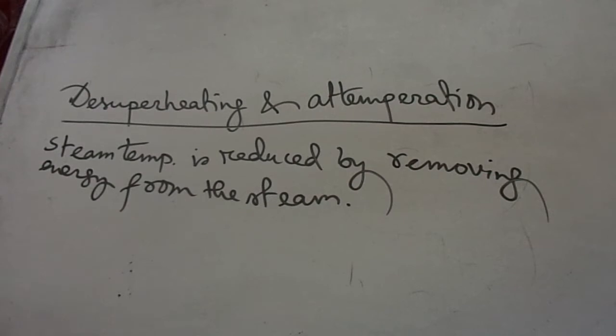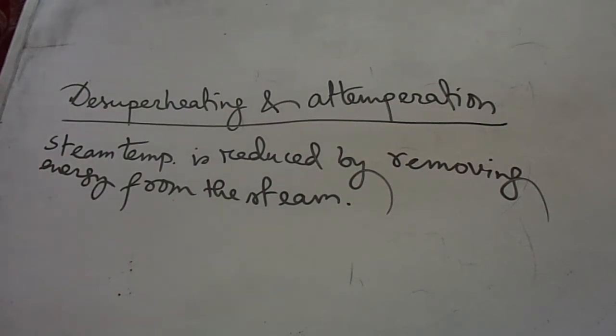In the tubular type, a portion of steam is taken out through tubes from a point between the primary and secondary superheater by an automatic valve and diverted to a shell and tube heat exchanger, where boiler water from the drum may be circulated.